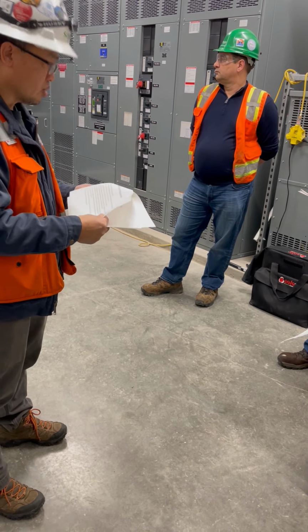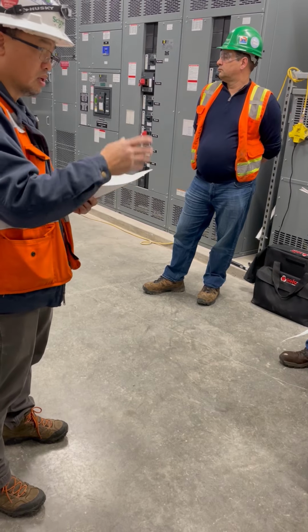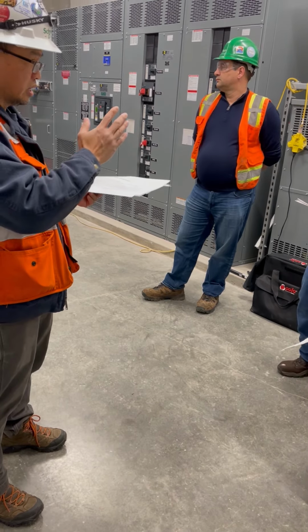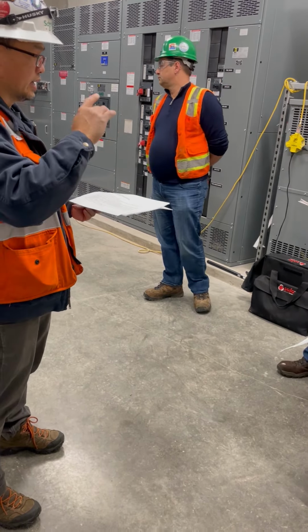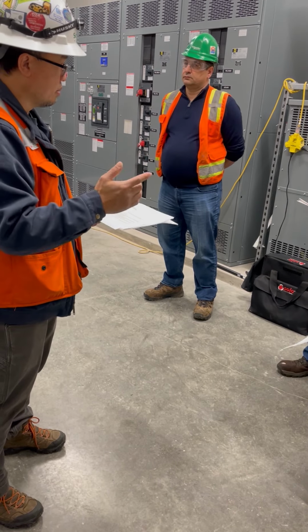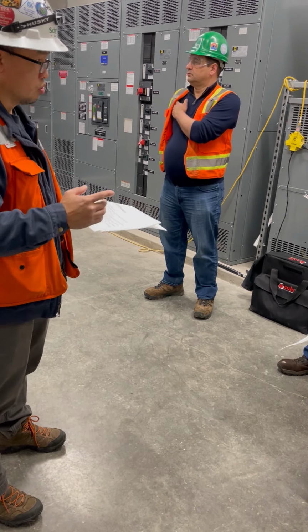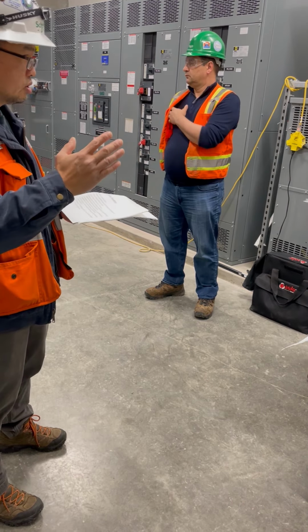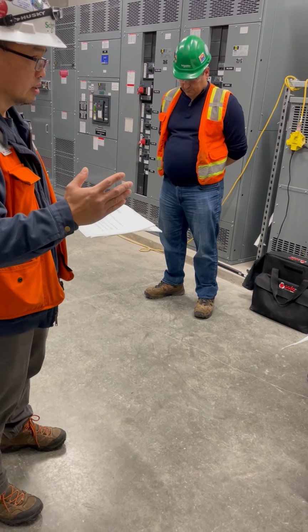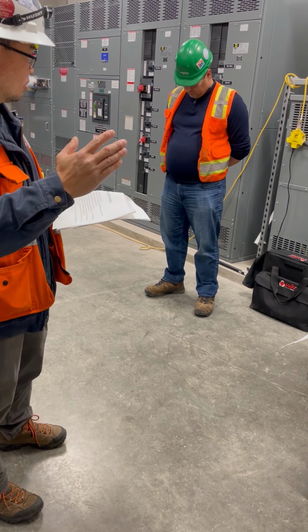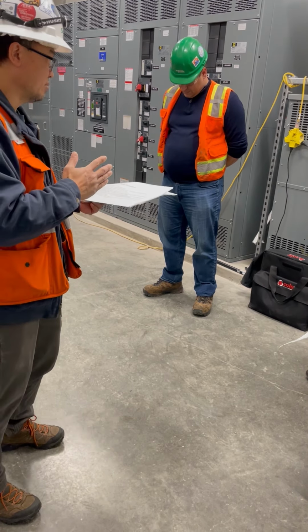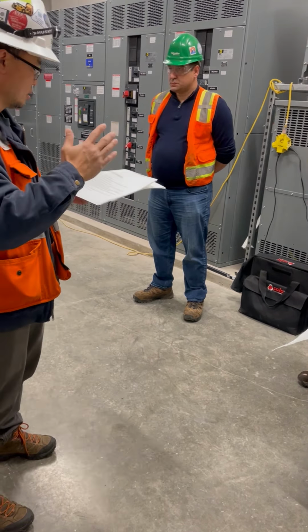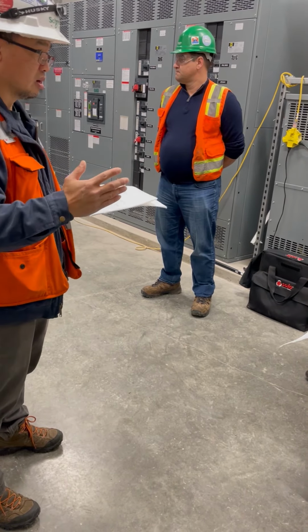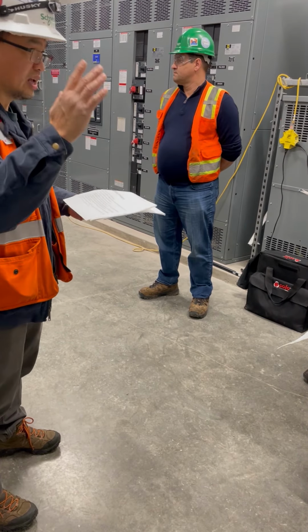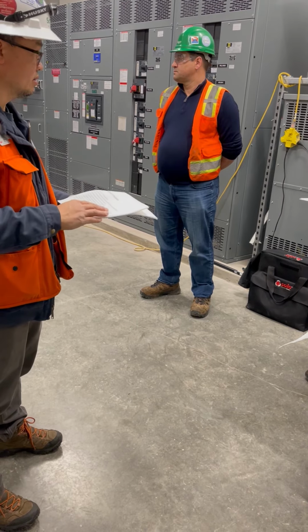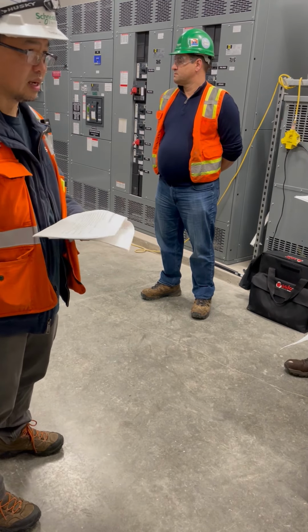But you also have to consider arc flash. Arc flash incident energy is determined by time and current, the available fault current. So if you set your coordination too high, your incident energy might be too high. So you have coordination, but your incident energy might be really high. There's a balance there, a little bit of an art. You can't just set everything high to coordinate, and you have to consider the human element side of it.